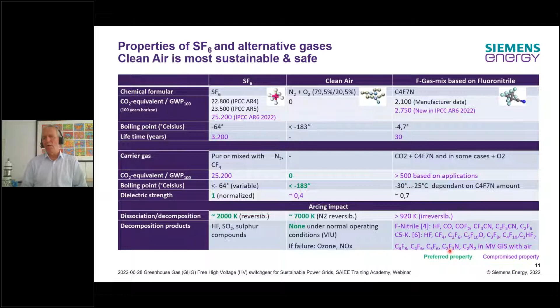So in order not to liquefy at -10 or -20 or -30 degrees, as is common in some parts of the world, it's mixed with CO2 and with O2. And then you have a mixed global warming potential, and you achieve lower operating temperatures down to -25. And the dielectric strength is then in between clean air and SF6. The biggest disadvantage of those gases is that once you start switching with them, they fall apart and do not recombine entirely. So after switching several times, you will have lots of different decomposition products listed here, and some of them are toxic, and that's the problem to handle.